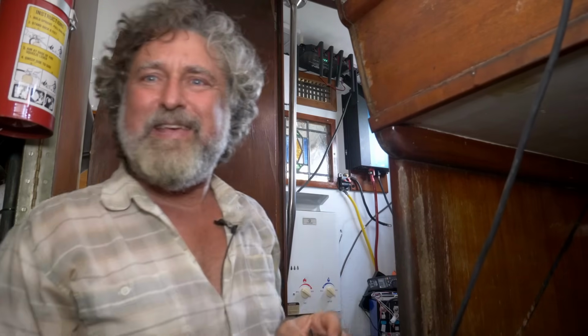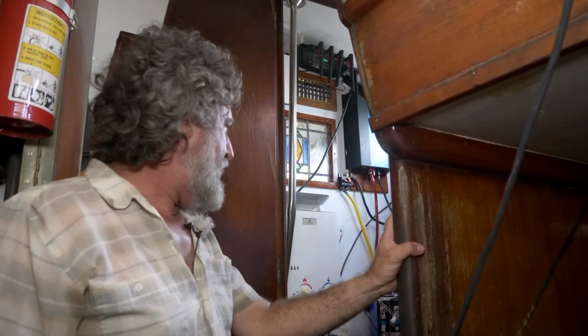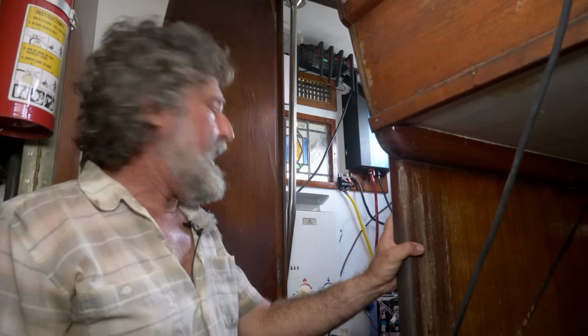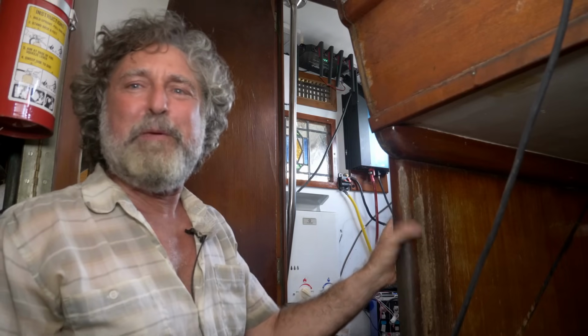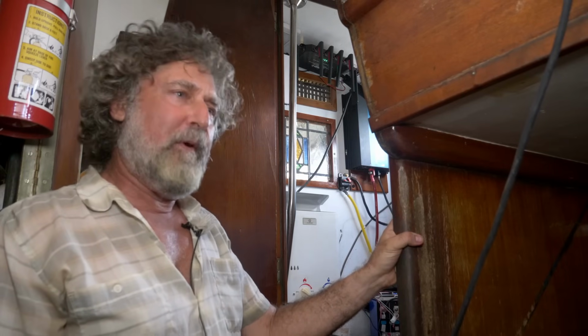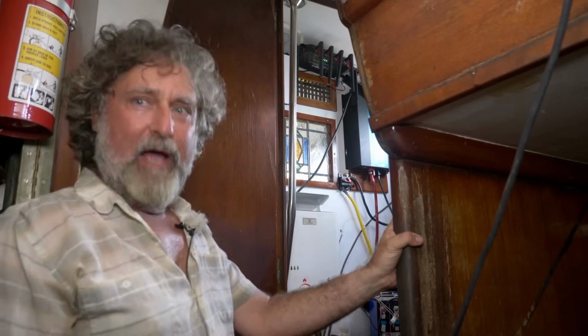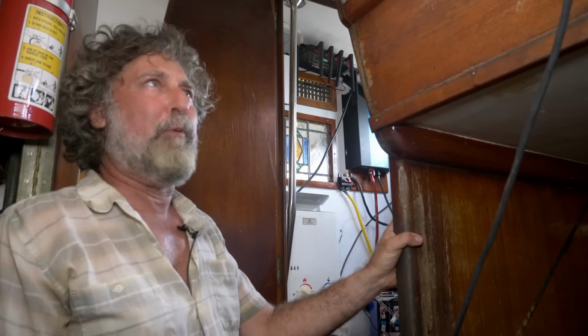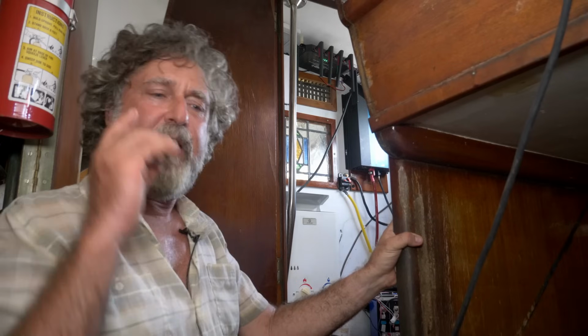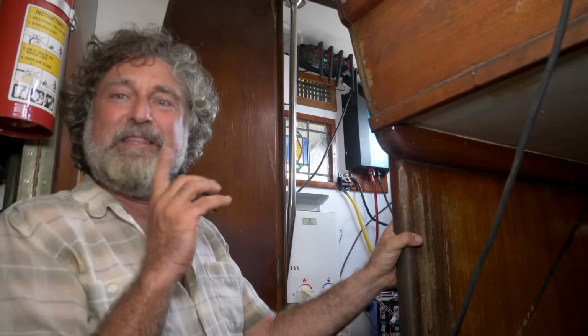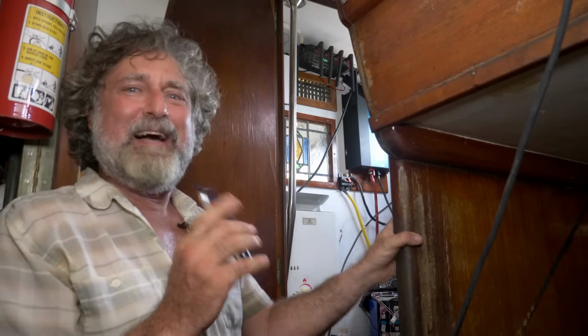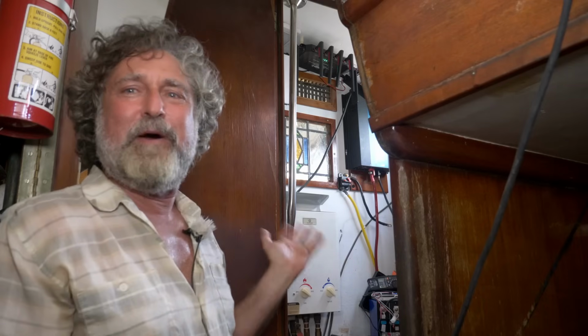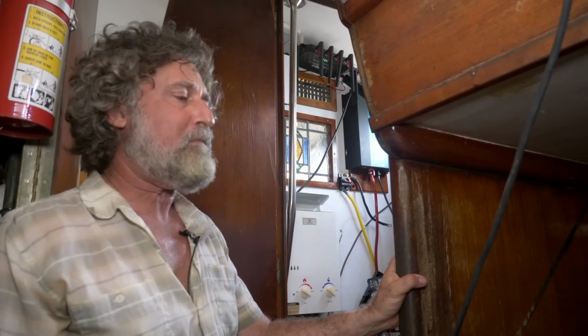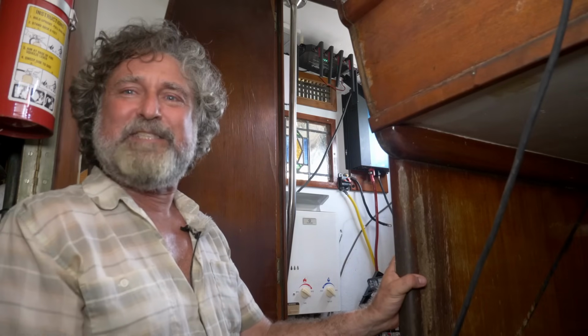Okay, got the test running again. Nothing is hot, and it shut off. And then it occurred to me why - it's rated for 100 amps, I drew 105. It's a proper digital device, it's actually watching what's happening, watching the actual amp flow. It's not saying I'll run it until it gets hot and whatever, like the cheaper ones do. So I broke the rules, so it shut down.